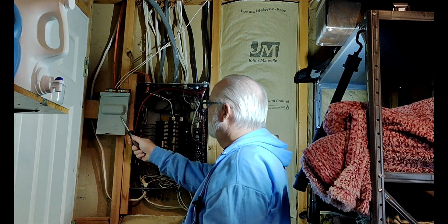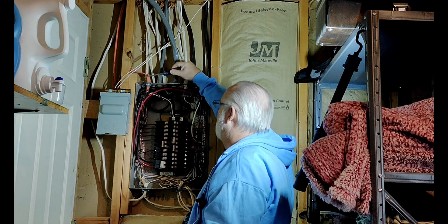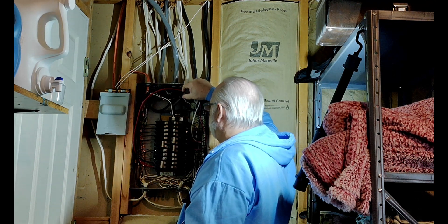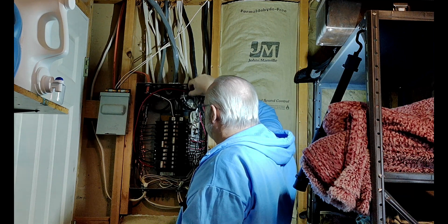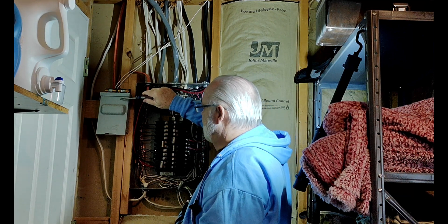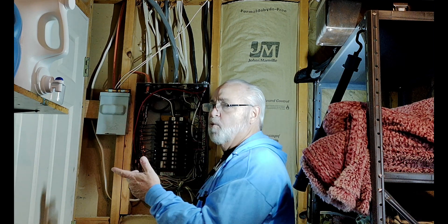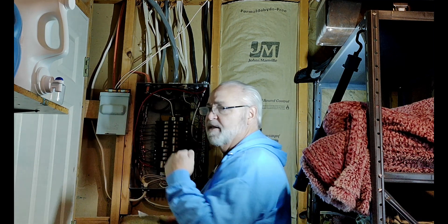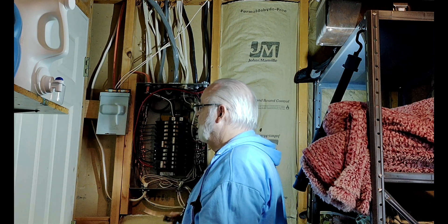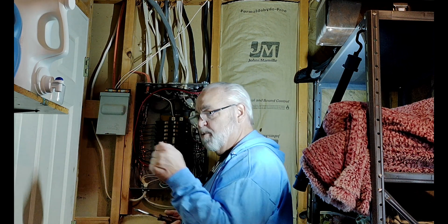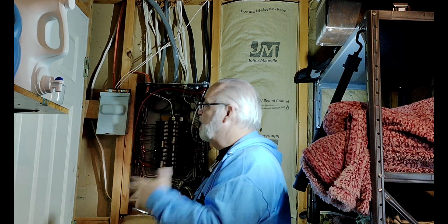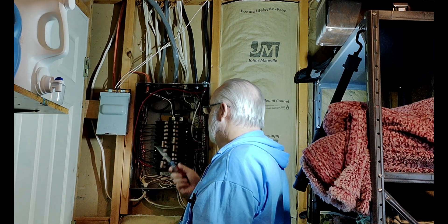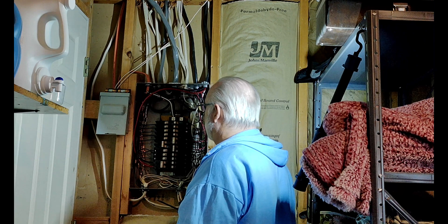Now, if you look at this box's wiring, it comes in on this orange Romex right here and goes right down into the two mains, and it's tapped into the mains. Evidently they thought this would be a good idea. This is actually supposed to be out by the AC unit, and that way if you have to work on the AC unit, you quick disconnect this box. Clearly, this was the dumbest idea I've ever seen in my life.